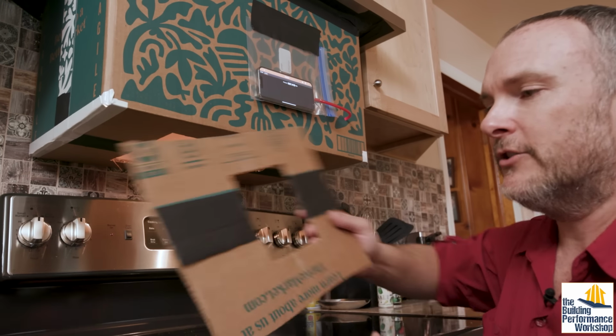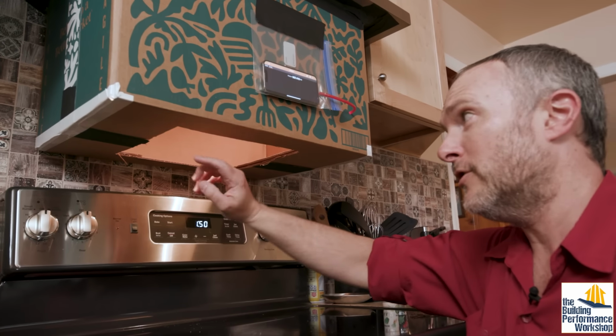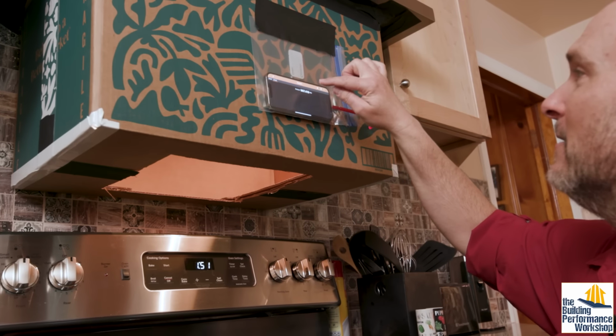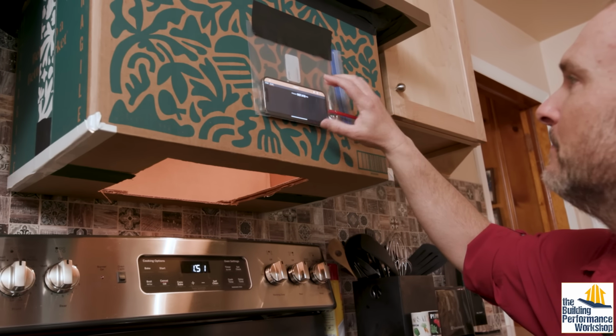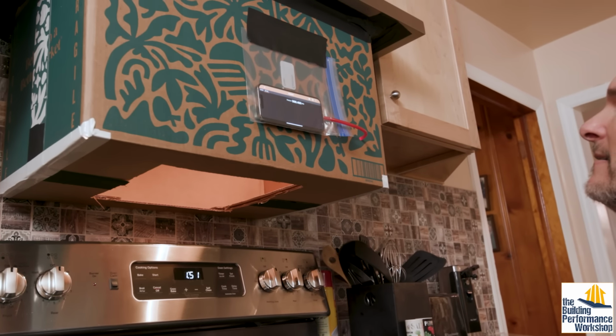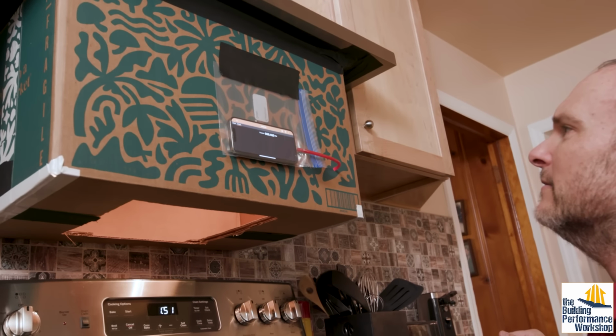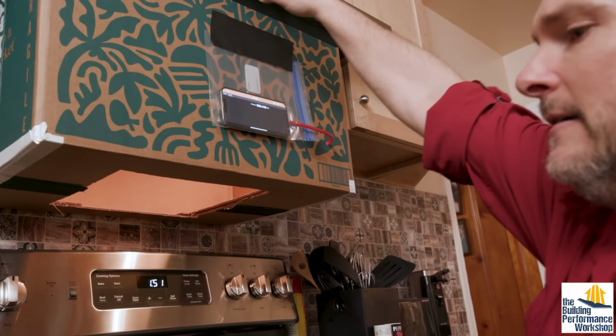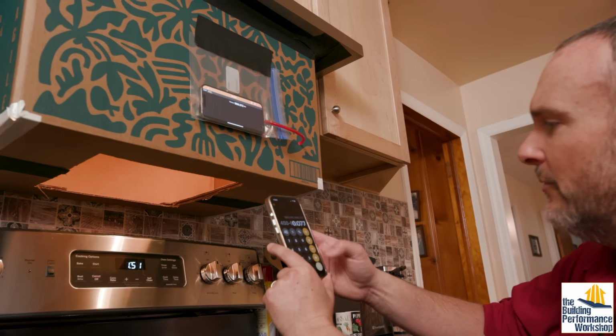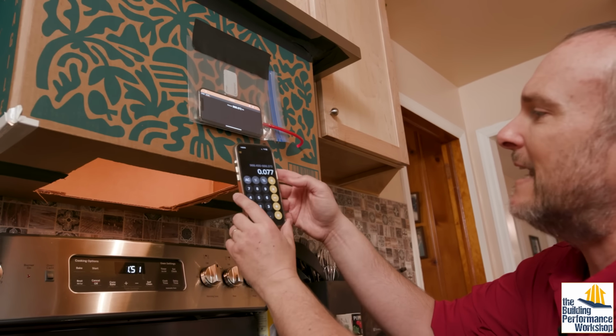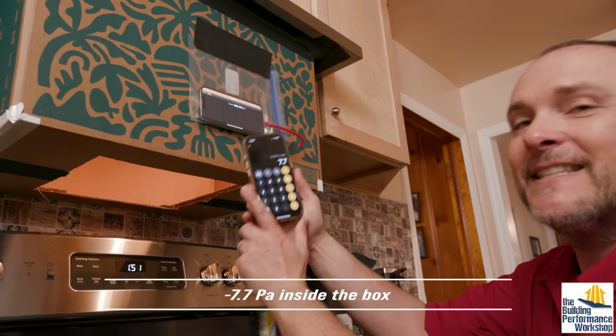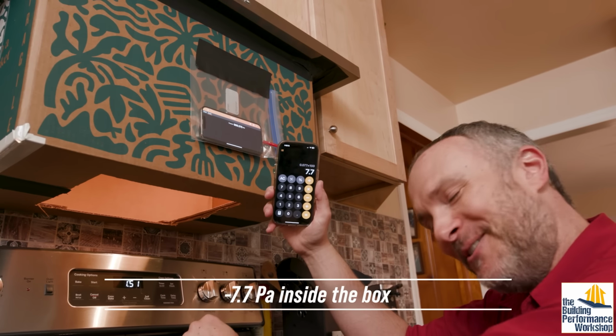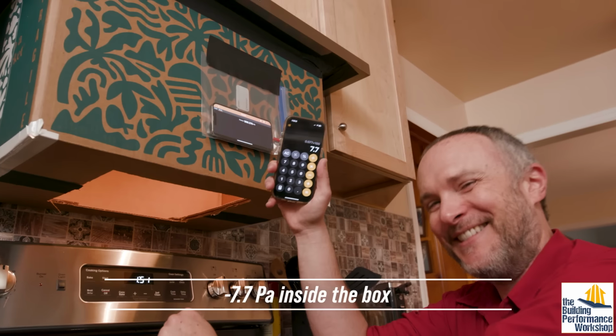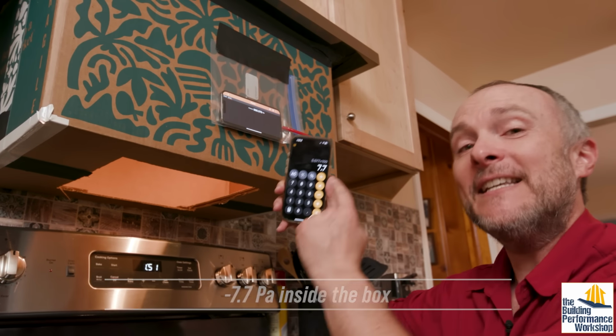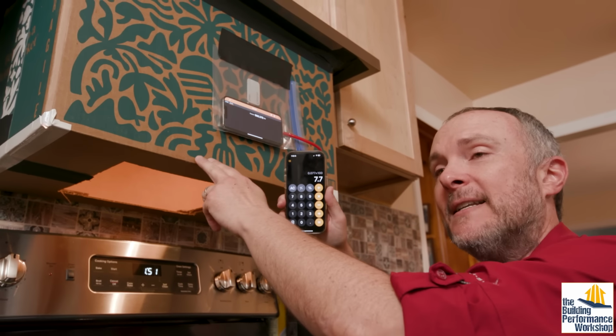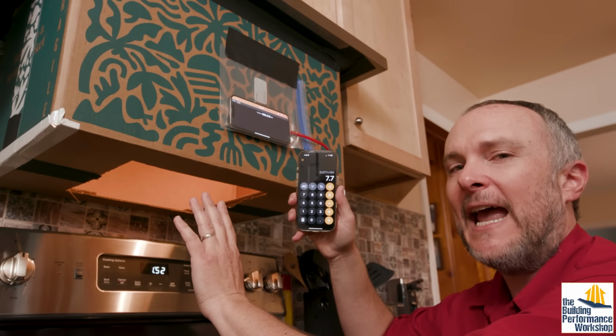Goodbye 5 by 4 inch hole. Hello, 11 3/4 by 10 inch. Now let's see, we're at 988.450 minus 988.373, and we end up with 0.077 times 100 is 7.7 pascals. Whew, thank God. I thought I was gonna have to recut that hole. Okay, so this is within the tolerance. We want it to be between 2 pascals and 8 pascals in here for as accurate as possible.